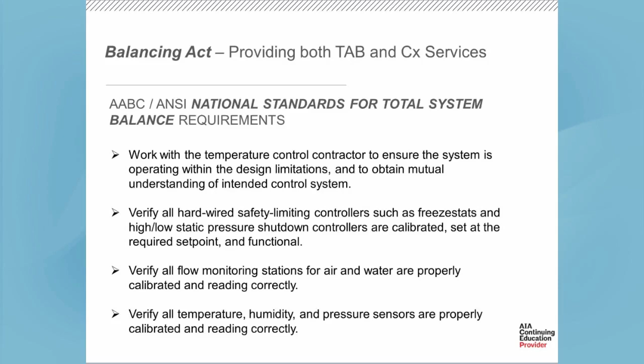So verify all the control devices are properly installed. Again, the test and balance firm is going to be out there in all manners of the ductwork and the piping, looking at flows, looking at pressure drops, things like that. They're the ones that are really the best to say, is the static pressure sensor for a variable air volume system in the best location? Because they know what's going on in that system.